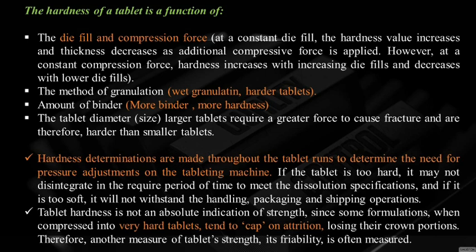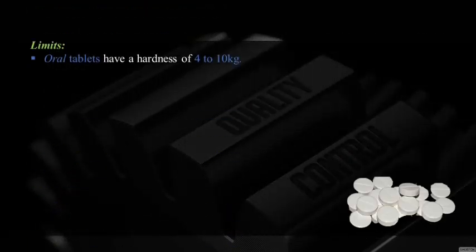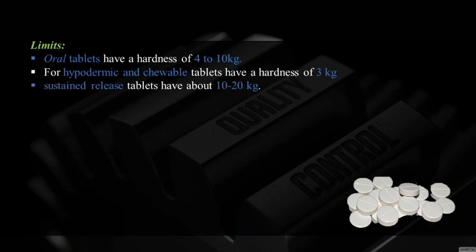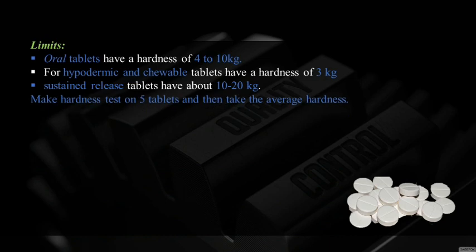Tablet hardness is not an absolute indication of strength, since some formulations when compressed into very hard tablets tend to cap on attrition, losing their crown portions. Therefore, another measure of tablet strength is friability. Hardness limits: oral tablets have a hardness of 4 to 10 kg; hypodermic and chewable tablets have a hardness of 3 kg; sustained release tablets have a hardness of 10 to 20 kg. The hardness test is made on 5 tablets and the average is taken.